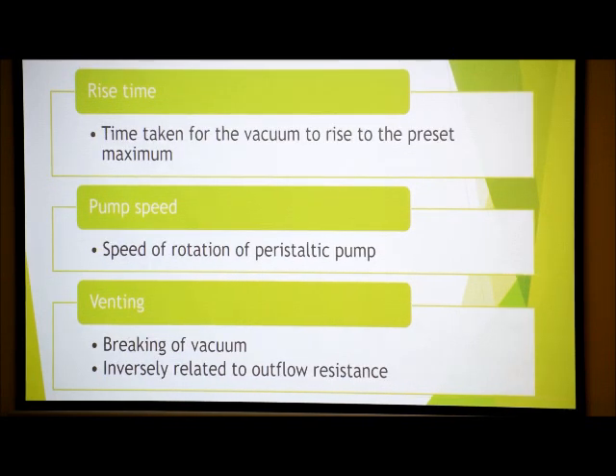Rise time is the time taken for the vacuum to rise to the optimum preset level from 0. Pump speed is the rotation speed of the peristaltic pump. Pump speed is regulated by movement of the foot pedal, and that helps in delivering more power during chopping and during segment removal. Venting is a protective mechanism when the pressure inside the probe builds up, and if there is sudden breakage of the fragment in front of the tip, then that is called surge. That is, fluid and particulate matter suddenly gushes into the phaco probe, reducing the volume inside the anterior chamber and collapsing the anterior chamber, which may lead to posterior capsule rupture.